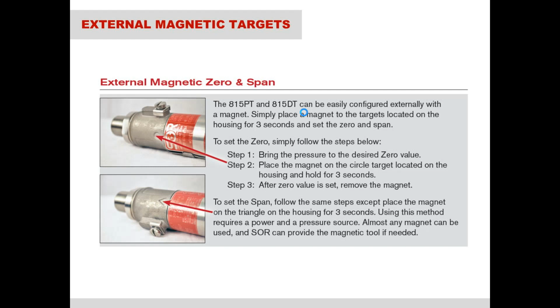If you just want to re-zero the transmitter, say you've had the transmitter out in the field for 5 years and the 0 has kind of drifted off a little bit, and say the 0 is supposed to be atmospheric pressure. Well, what you can do is just expose that pressure port to atmospheric pressure and then hold a magnet there for 3 seconds, and it will reset the 0 to atmospheric pressure. Now, a lot of people talk about, well, what happens if some Joe Schmo goes up there and is holding a magnet, and what's the security risk of that? Well, if that's really a factor and that's really an issue, you can go into the software and turn off those magnetic targets if you need to.